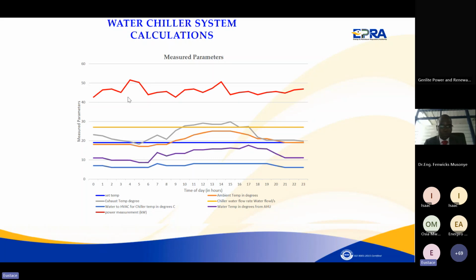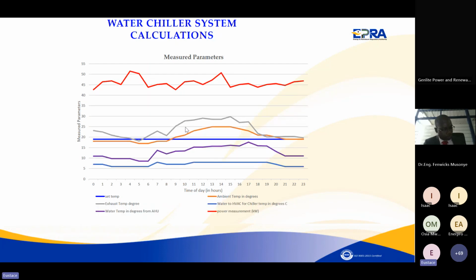Or probably at this point is when people come into these data centers, and there is a lot of influx of air from the external through the door. You want to see whether the air curtains are functioning well, to warrant all this, or whether it is bad behavior of people. So you have to establish all these abnormalities, because you don't expect the power to go on when the temperatures are very low, especially early in the morning, and especially if it was not raining. Because if it was raining, you can conclude it is because of the latent cooling.